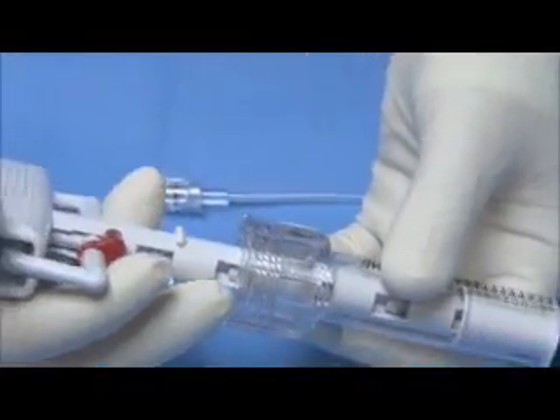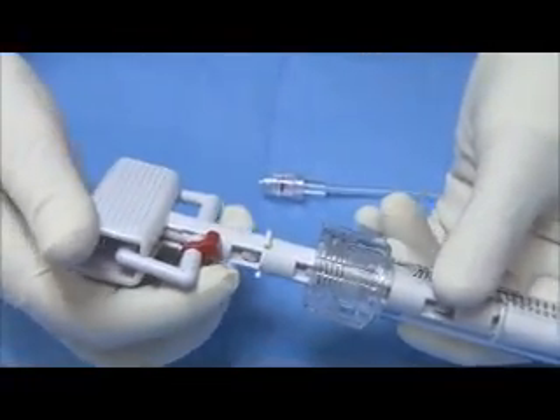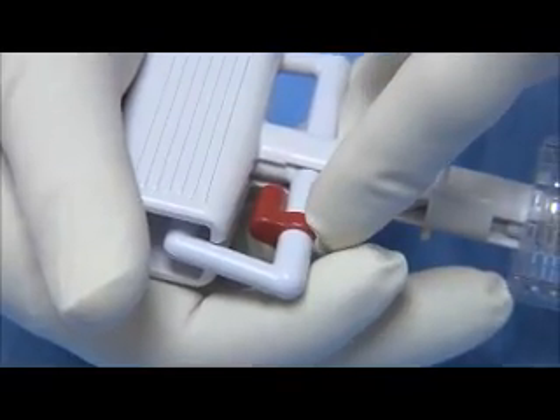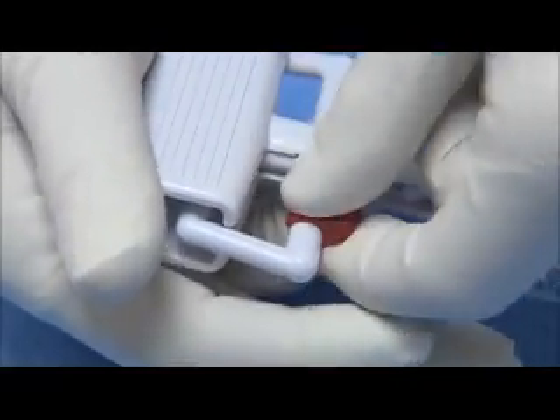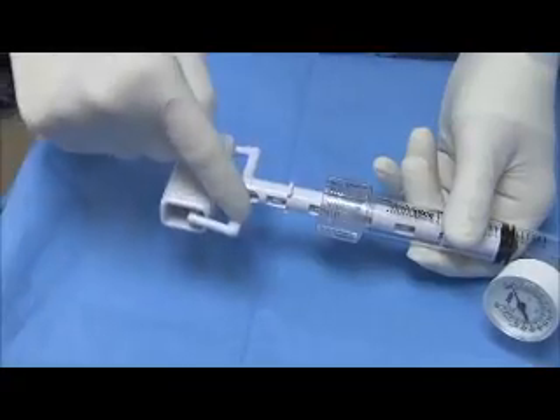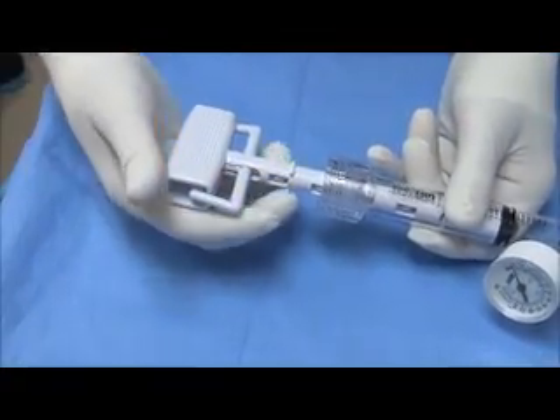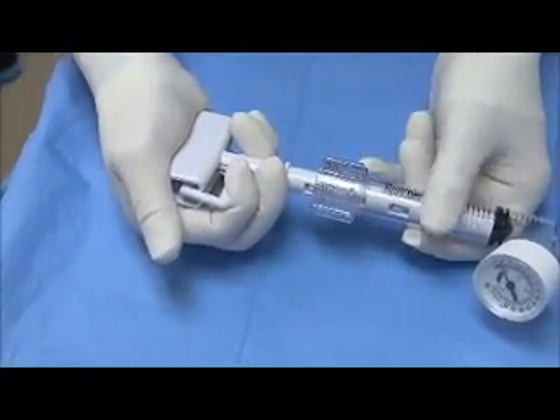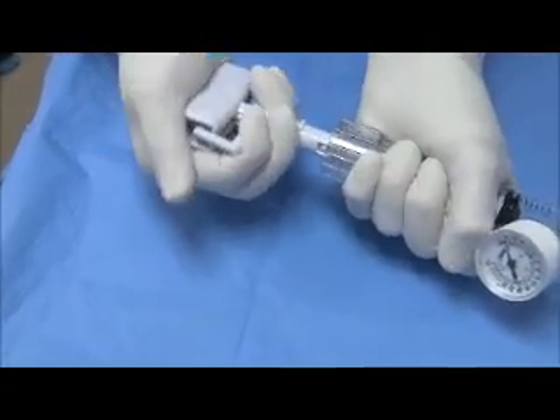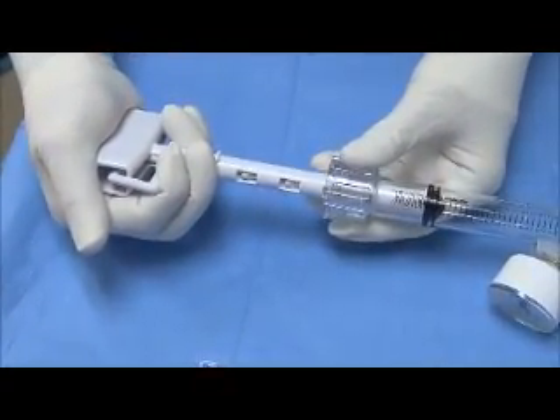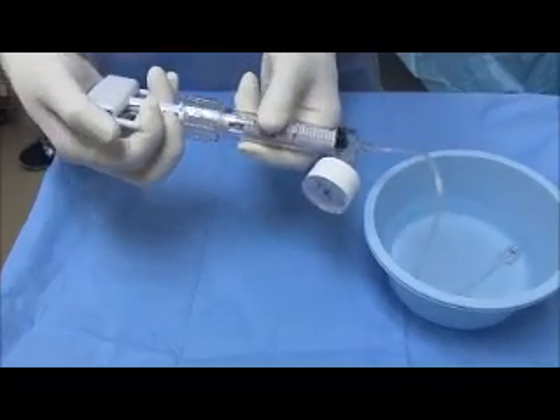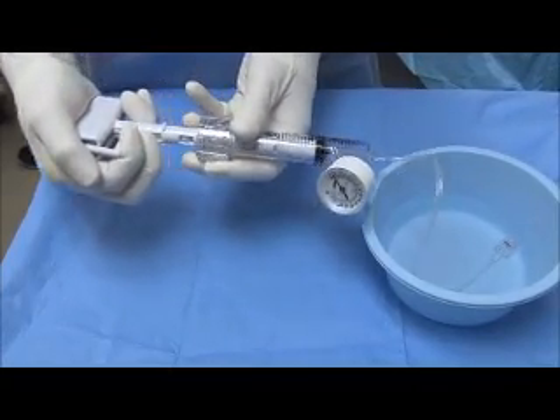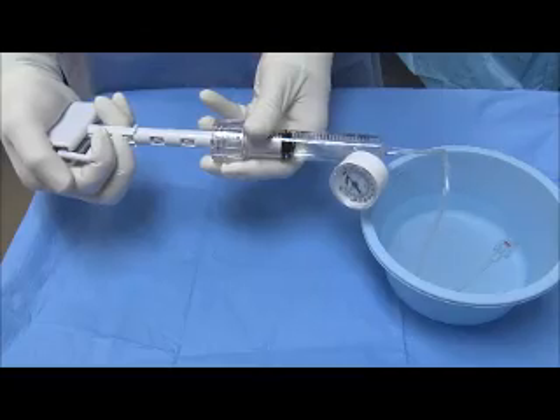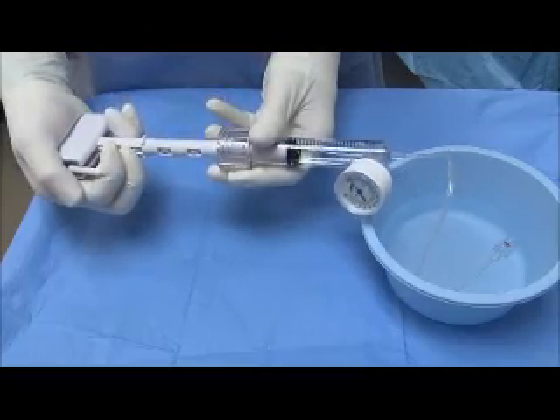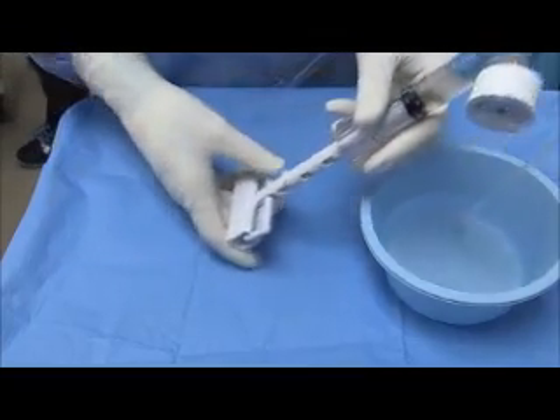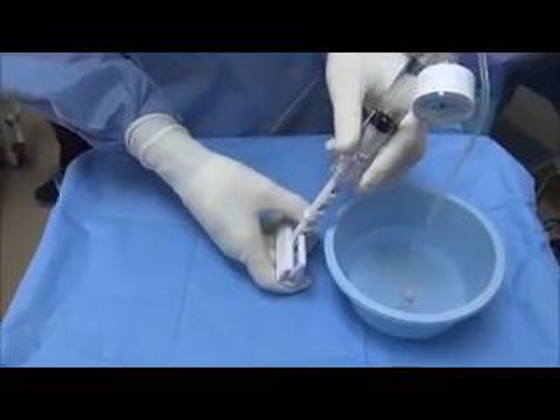There's a handle on the proximal end of the balloon. It comes with this red stopper here, so you want to remove that before you use it. This is the lever, and here's the handle. When you squeeze this lever, this becomes a giant syringe, and you can just suction that back. So you put that in some water, squeeze the lever, and pull all the way back, as far back as you can. Turn it upright to get the air out of this, and push, get all the air bubbles out.